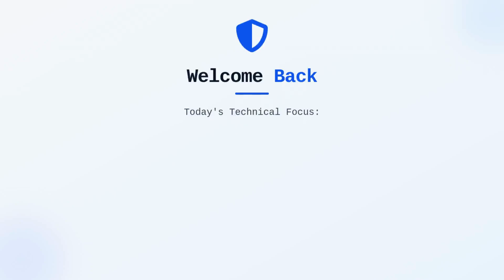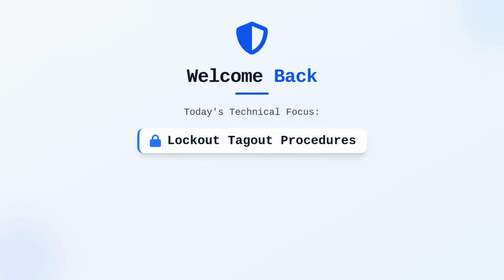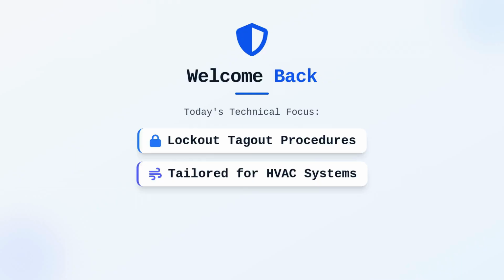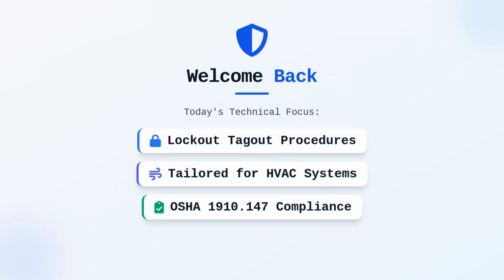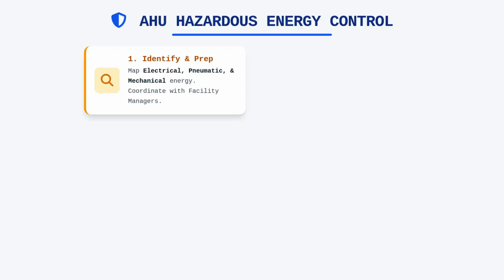Welcome back. Today, we are focusing on lockout tagout procedures, specifically tailored for HVAC systems to ensure you maintain full compliance with OSHA 1910.147 standards. Working on air handling units involves interacting with various hazardous energy sources that can cause serious injury if not controlled properly. Before you begin any mechanical cleaning or inspection, you must identify every potential energy source, ranging from electrical feeds and compressed air lines to stored mechanical energy in belts and fan assemblies.